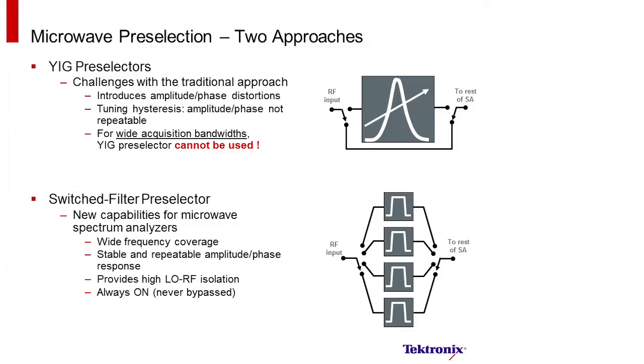So we've seen the two different approaches for the use or the implementation of microwave preselection. With the Agilent PXA, a YIG preselector is used. This is a traditional approach. There are a lot of advantages to using this approach. However, the big disadvantage is for wideband acquisitions, the preselector cannot be used due to the nonlinear nature of YIG preselectors, especially for wider bandwidths, wider than about 40 megahertz.